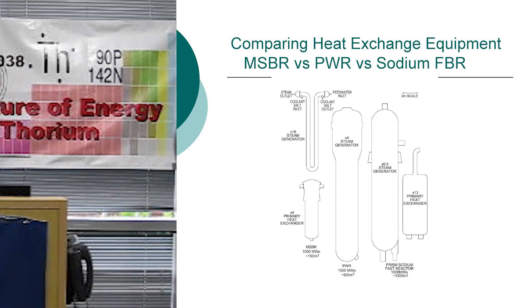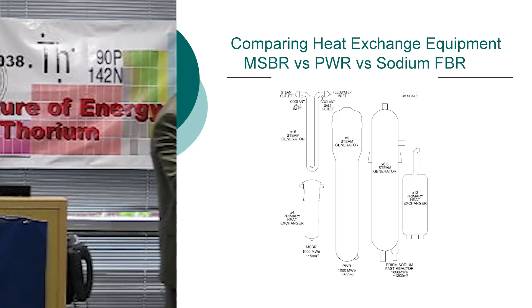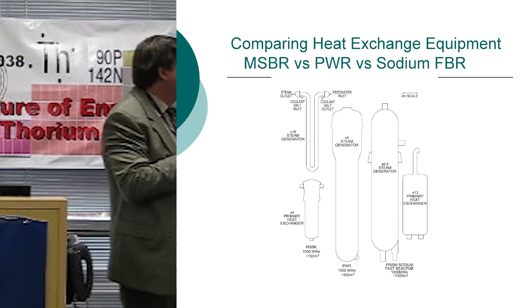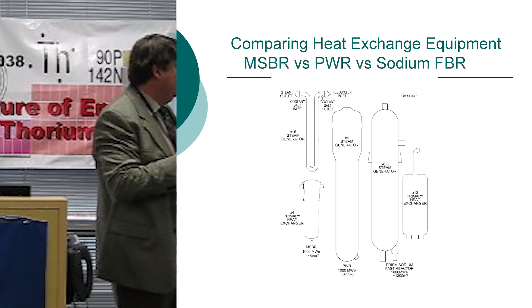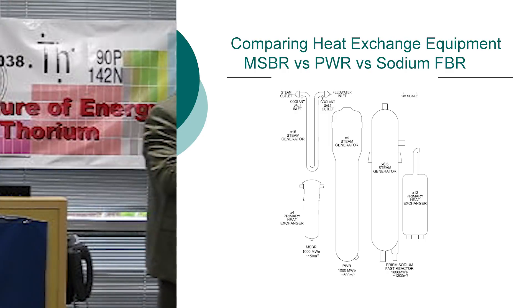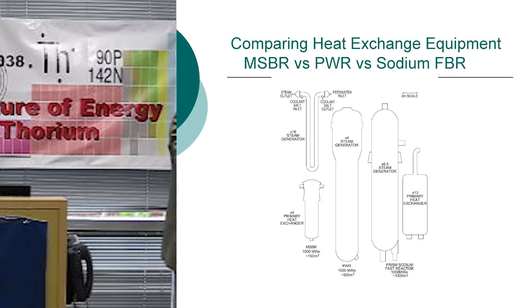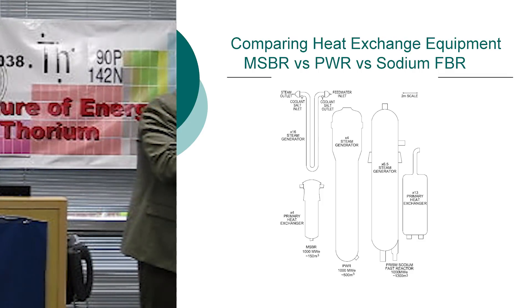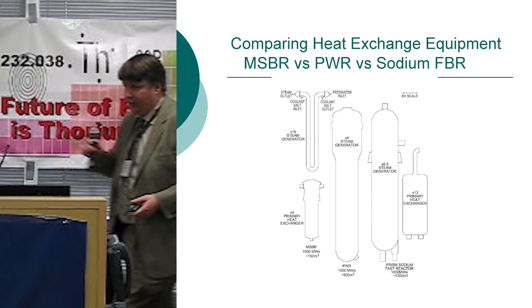The two components on the left are the steam generators and the primary heat exchanger — there are four primary heat exchangers for 1,000 megawatts, with sixteen of these little U-tubes involved. Compared to a PWR with a massive steam generator, and compared to a fast breeder with the poor nature of sodium, there are about six and a half incredibly large steam generators and 13 large primary heat exchangers in the PRISM design. So there's a lot of potential savings.